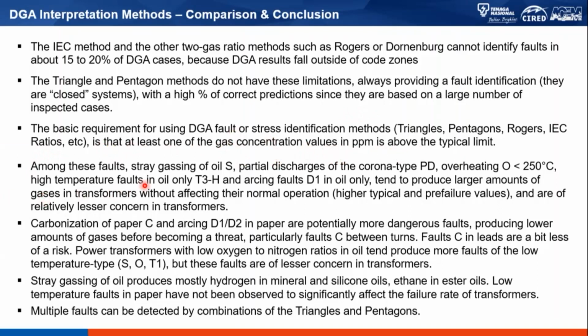Among these faults, stray gassing of oil is indicated as S, partial discharges of the corona type as PD, and overheating of oil less than 250 degrees. So these are all the complementary fault characteristics that are newly developed, and most of them can actually be detected if we are using the pentagons developed by Mr. Duval. Okay. Carbonization of paper, C, and arcing, for example D1 and D2 in paper, are potentially more dangerous faults, producing lower amounts of gases before becoming a threat.